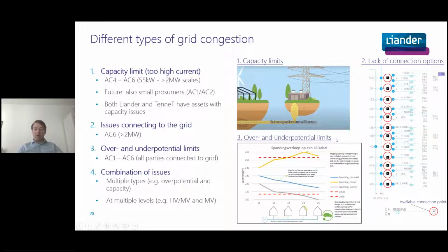Then there are over- and under-potential limits. This already affects small consumers too. If you have a cable, and at the end of it there's solar energy, the potential can become too high - the over-potential limit. And when it's heat pumps, electric vehicles, or other loads, the potential can become too low. These limits are stated in the net code Electriciteit for power quality, and this can also become a problem.